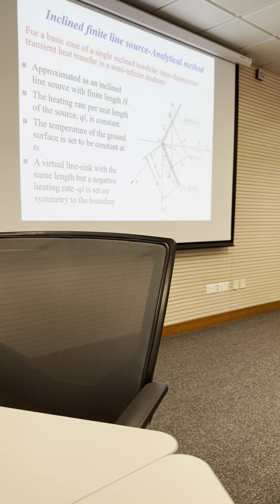That is another assumption. In fact, it's not, because the ground temperature is not constant. Deeper, it may be lower or higher, depending on the region, on the area. But here we have to consider that the heat transfer from the line source, the borehole, is constant. I mentioned that for any analytical solution we must make some assumptions. Then we can solve the partial differential equation.